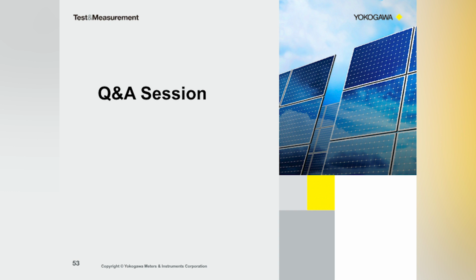Would there be a difference in uncertainty between a single-phase power measurement and a three-phase power measurement? Yes, there will be. When you're measuring a three-phase system, you're going to have three different voltages and three different currents, so there will be a slight uncertainty difference. In fact, on our power analyzers, we have an uncertainty calculator that calculates uncertainty on a single phase, a three-phase three-wire system, and a three-phase four-wire system.